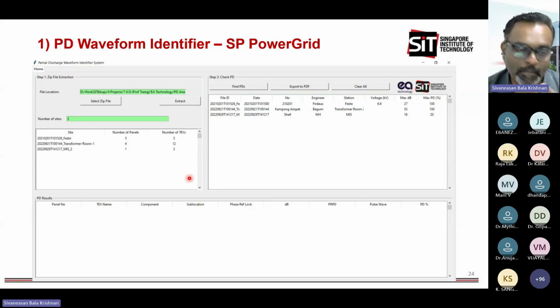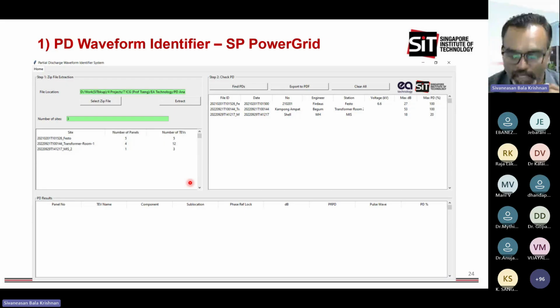One of them is PRPD plot. So we also look at a few things. We look at number of pulse per peak, number of times they exceed the threshold. How we get the threshold is we determine by the mean and the standard deviation. And we also look at the pulse width. How, every pulse, how much is the width? So if the width is greater than 2 microseconds, then it's something more severe, that kind of thing.